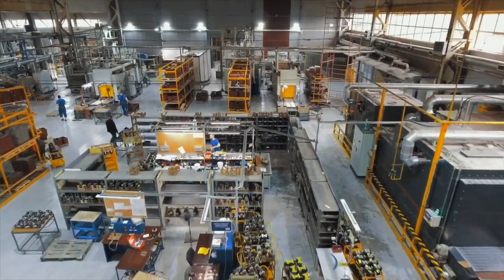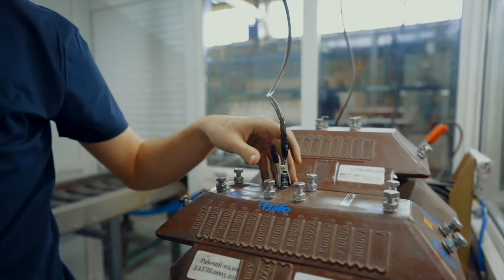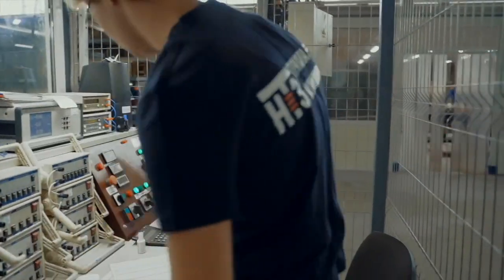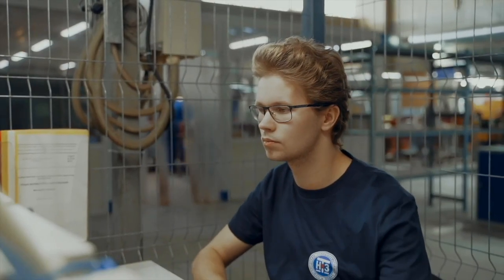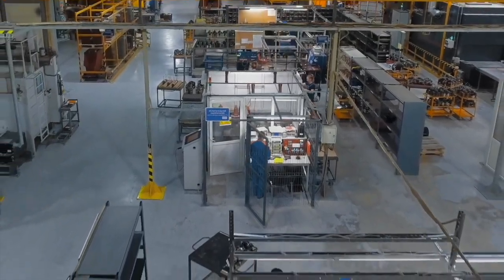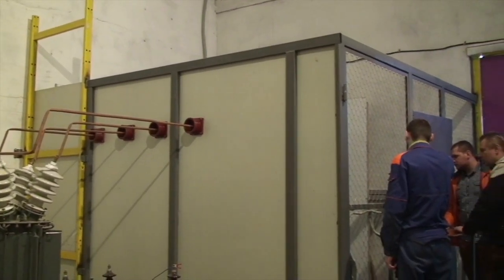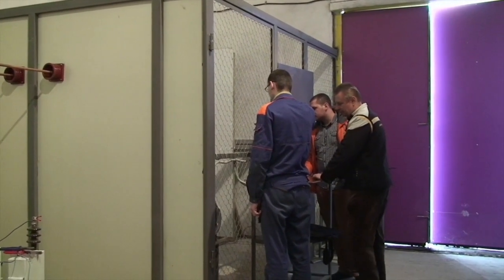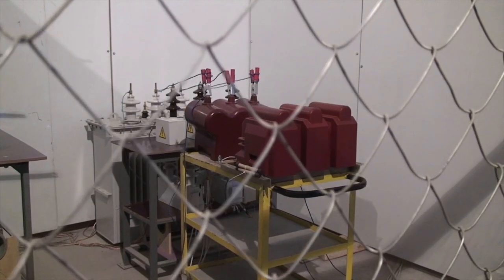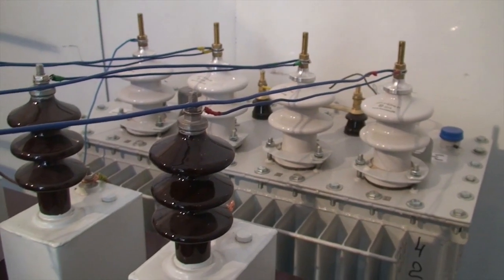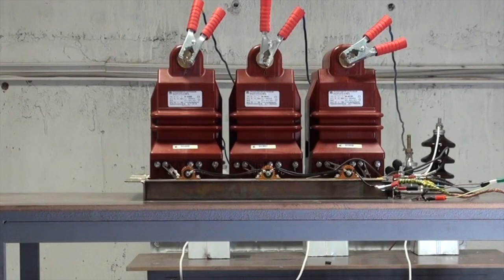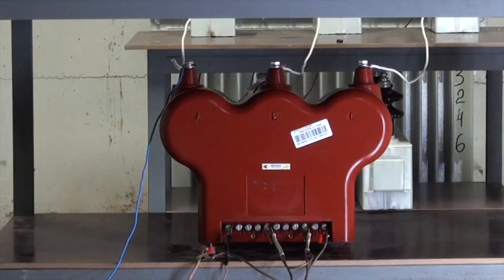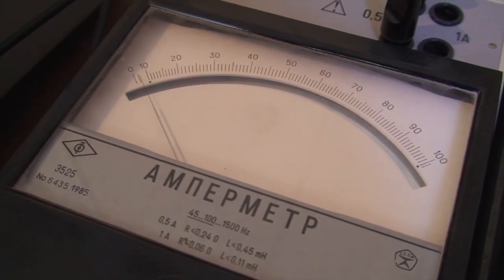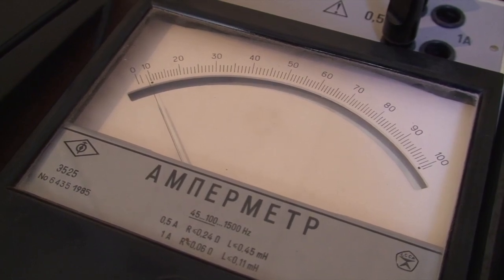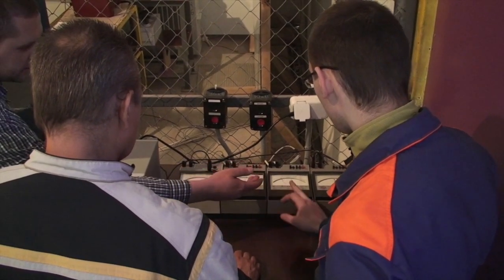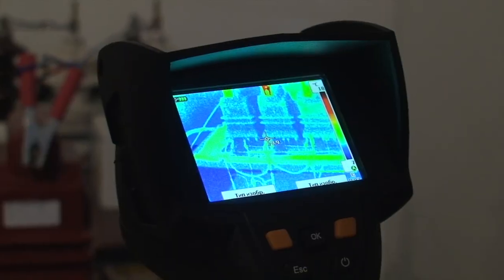Let us give an example of testing voltage transformers for resistance to the most common cause of transformer failure, intermittent arc single-phase phase-to-earth faults. The laboratory setup for testing in this mode includes a power 3-phase transformer of 100 kVA, a set of network capacities, an arc phase-to-earth fault device, and recording and measuring devices. To carry out the test, NTZ Volkhov specialists connected two types of voltage transformers to one network. The testing process is controlled by ammeters, voltmeters, an oscilloscope, and monitoring the temperature of both types of transformers using a thermal imager.